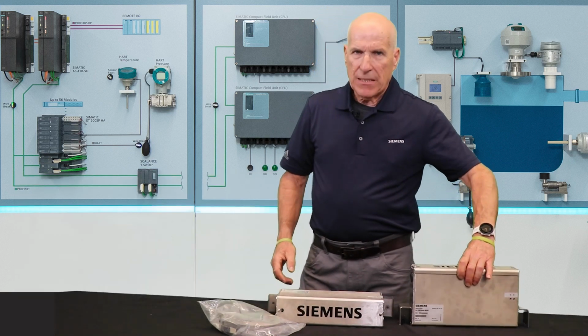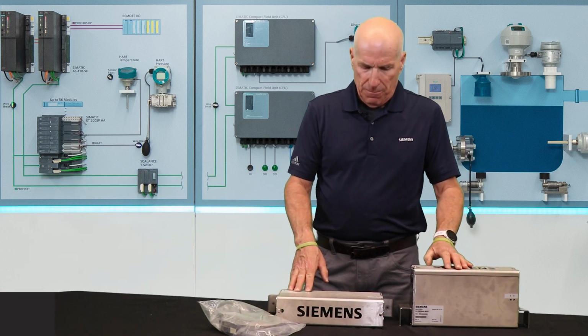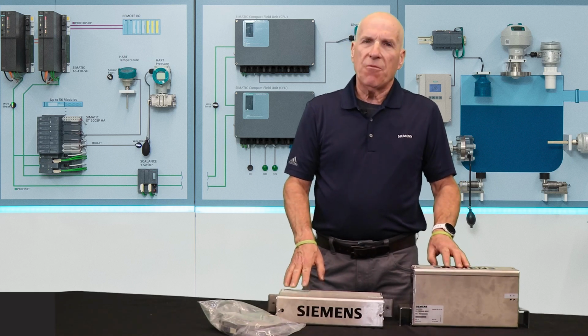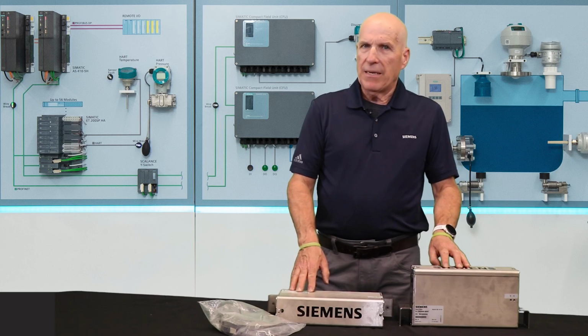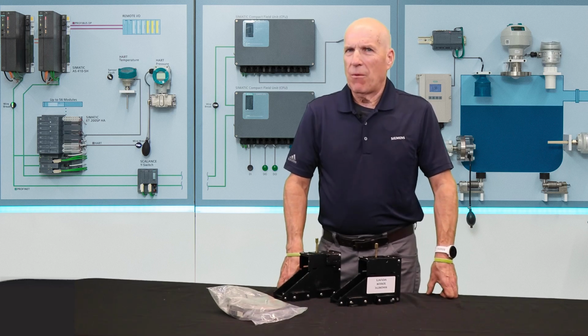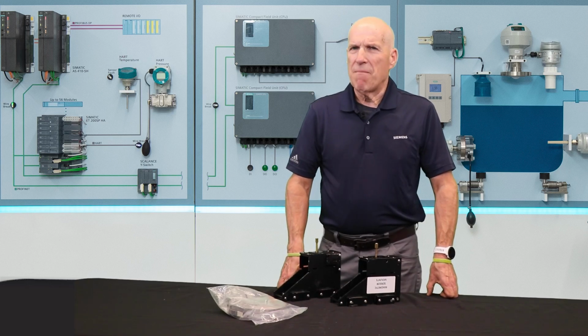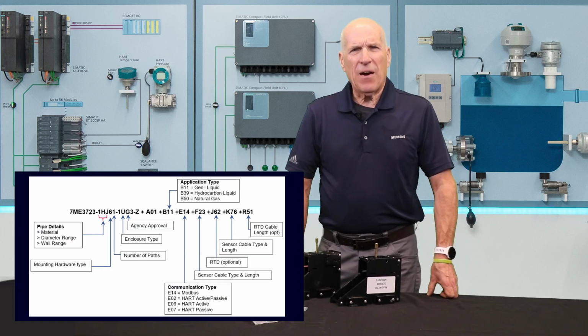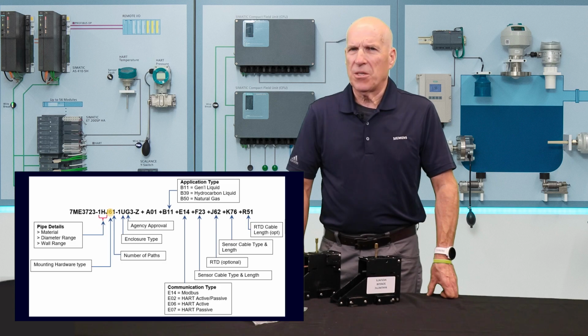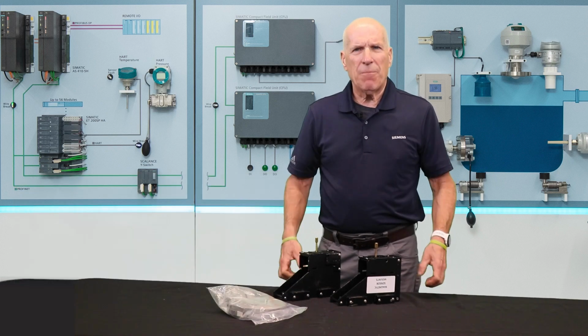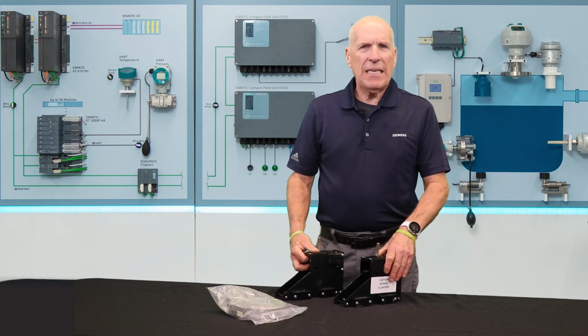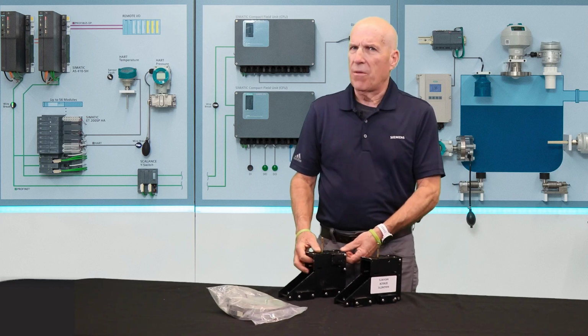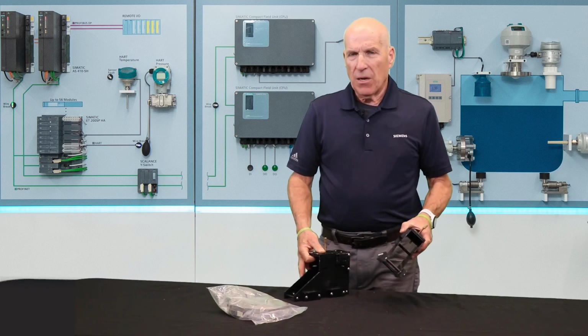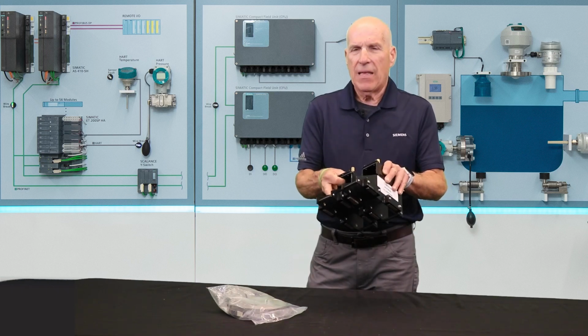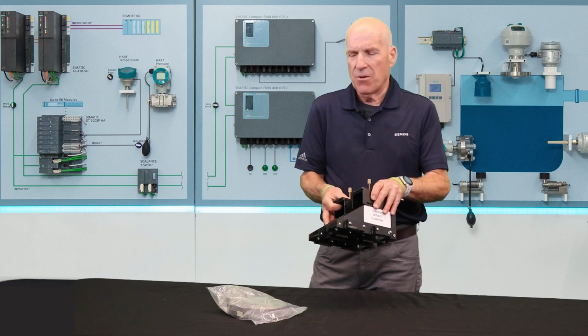Using dual enclosures, the spacing between the sensors is set utilizing a spacer bar. High precision mounts are typically found on hydrocarbon pipeline and natural gas pipeline applications. In addition to all the standard mounting hardware that we've just reviewed, there's also the availability of magnetic mounting frames. These are identified by the number 6 in the system part number position 11. These can be ordered for any pipe that is a ferrous metal where size C, D, or E sensors will be used, whether they're high precision or universal. They utilize extremely strong rare earth magnets that will hold the transducer securely in place on your pipe.